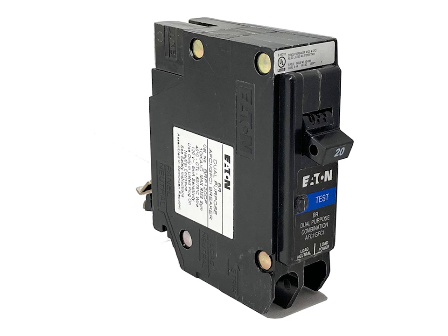However, any current in the neutral wire will trip these breakers. We had a large coronal mass ejection, CME sunspot, the activity that causes the northern lights. When this solar storm hit the earth, we had 6 circuit breakers trip. If you don't happen to be home and any of these circuits are for a critical function, such as your boiler pump or your freezer, you are toast. Be aware that these breakers are sensitive.